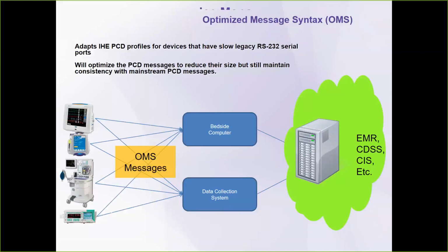While with the proliferation of the devices that we're talking about, many of the newer ones are IP native or even have wireless connectivity, and that's constantly increasing, there's still a number of old devices in the field that use interfaces that are serial-based connections. They use these for the purpose of data collection, and there's a hardwired connection to the back of them. These types of connections can lead to bottlenecks in the ways that they transmit data without proper management because they do tend to flood.